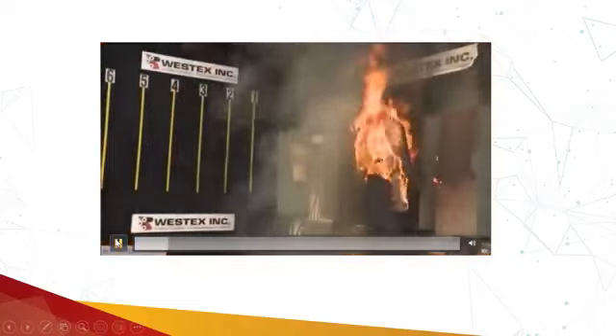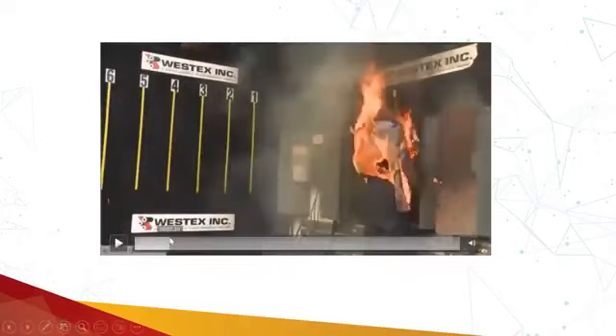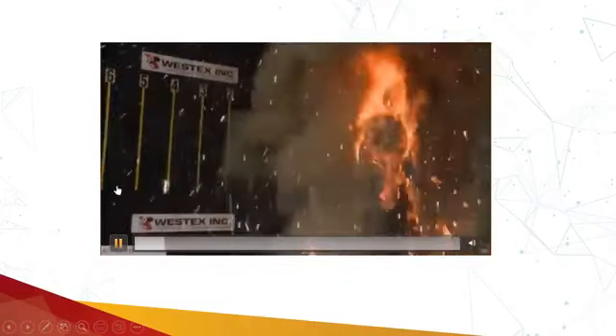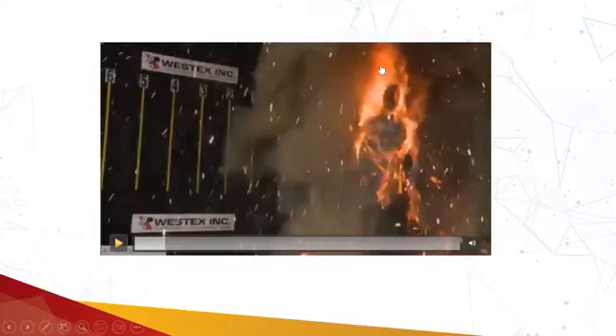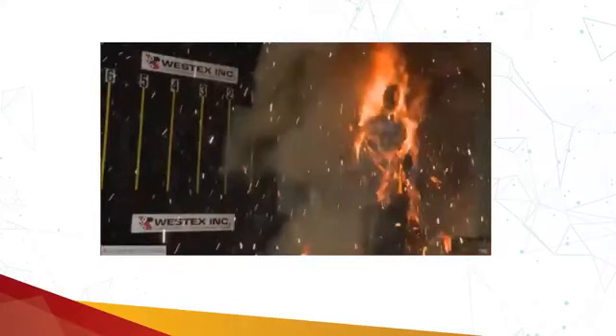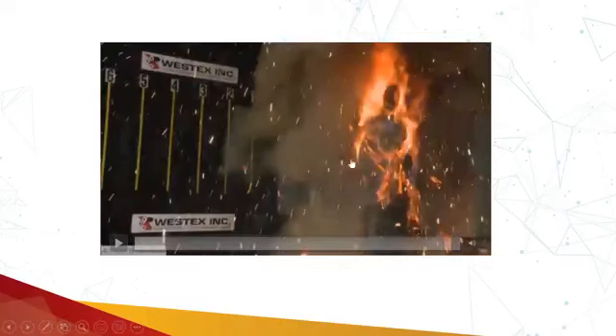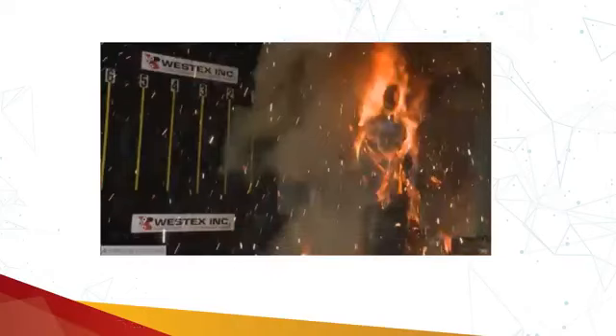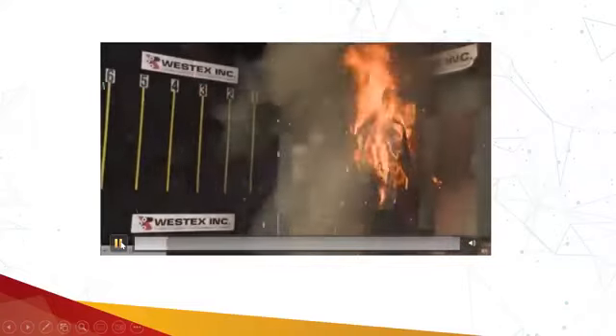We have a large arc and an immediate fire. And notice that the back of the garment is on fire. So basically, due to this arc, the amount of energy which is incident on a person, and he got burned due to this arc, that is going to fall under the arc burn. And once the arc is over, the person will continue to receive burn due to the hot gases, molten metal, and the fire on the clothing. That is going to fall under the thermal burn, third category.